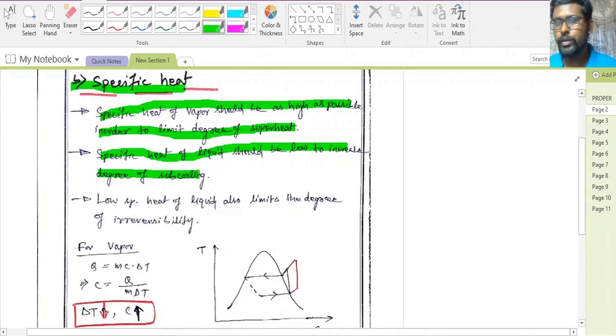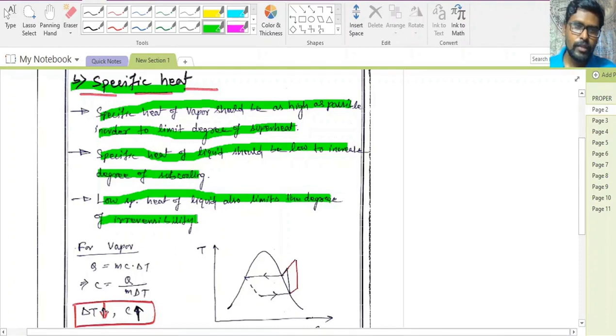The compressor work input will increase. In case of liquid, the specific heat of the liquid should be low to increase the degree of subcooling. If you increase the degree of subcooling, then the refrigerating effect will increase, and the COP will increase. Low specific heat of liquid also limits the degree of irreversibility. If the specific heat of the refrigerant in the liquid state is low, then the irreversibility in the system will also be low.